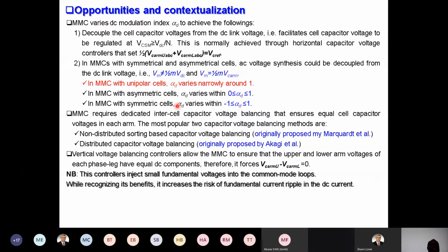And the MMC requires dedicated intercell capacitor voltage balancing that ensures equal cell capacitor voltages in each arm. Why is that? The cell has to be regulated because the IGBT will see the voltage across the capacitor. So the overvoltage across the cell capacitor will be seen by the IGBT, or by the semiconductor, as overvoltage. So you can damage your semiconductor devices. This is why capacitor voltage balancing is a very important component of the MMC.